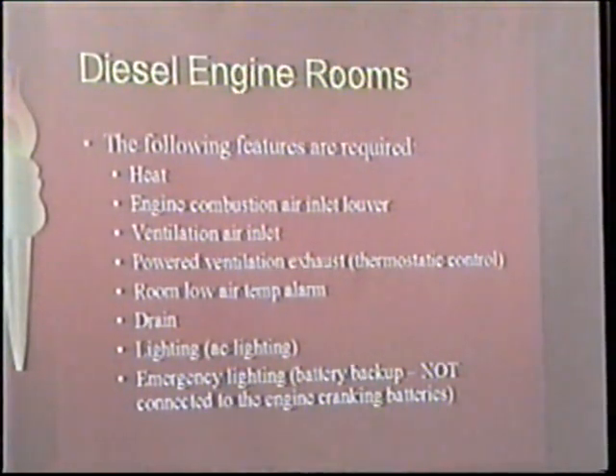The ventilation's important because we get fumes coming off of these engines, just like your car engine. The breathers coming out of the crankcases put oil fumes in there. The heat that the engine dissipates is about a third of the horsepower fuel that it burns, coming back as radiated heat. So to think that the room's not going to get over the 104 degrees that the engine's designed to run at on its rated horsepower curve is ridiculous. That room will get so hot so fast if it's closed up with no ventilation that you will lose horsepower and you will lose pump performance.